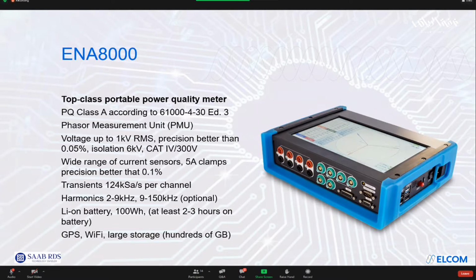It can also work as a portable phasor measurement unit, which is quite unique. It has high precision, measuring up to 1 kilovolt, category 4, higher isolation. It can be equipped with a list of sensors for different current measurements, from a few amps up to thousands of amps, using Rogowski coils.